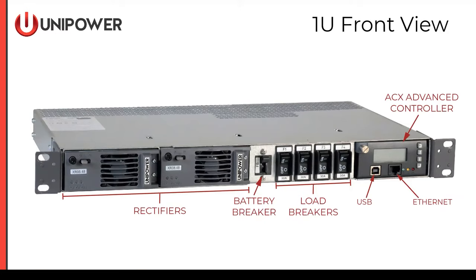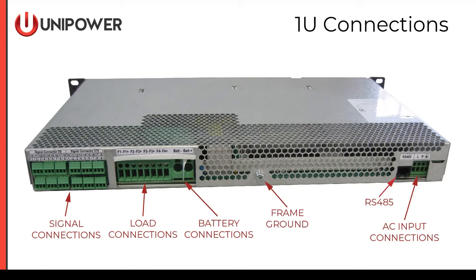Then we have the ACX Advanced Controller, which is used in all of the Aspiro and Guardian products. The Advanced Controller supports remote sessions via USB or Ethernet, and we also have support for SNMP V3. The chassis can be mounted in a 19 or 23-inch relay rack. On the rear, we see the battery hot connection and return, a frame ground, an RS-485 connector, and AC input connectors. The AC input supports a single bulk feed or a dual feed, so each rectifier slot can be fed with an independent feed.